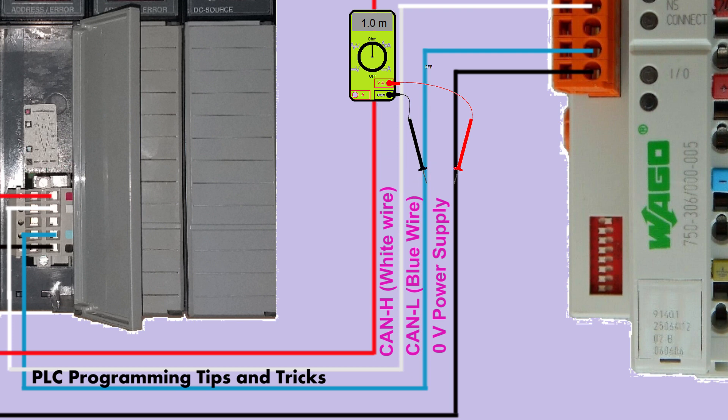This can be verified by an ohmmeter. The resistance between these lines must be above 1 mega ohm. These are some of the tips which are useful for troubleshooting a faulty DeviceNet network.